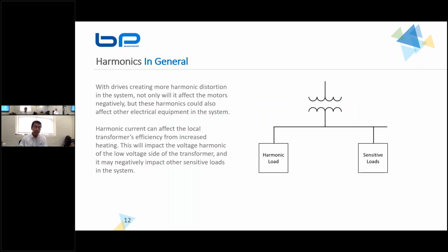And the way harmonics damage other loads, right, is that harmonic distortion can migrate within this closed-loop system. Your harmonic distortion may not impact the motor itself. Like if you have a VFD paired with a motor, the VFD generates harmonics, but it might not directly impact the motor. But that can go back onto the rest of your distribution system and damage other sensitive loads. We've had several clients with issues where harmonics migrate from one load to another, and it starts cascading because you have a bunch of loads generating harmonics, and in turn they resonate and receive harmonics from other places. That's when you'll have systems failing and a lot of drives running into heating issues.